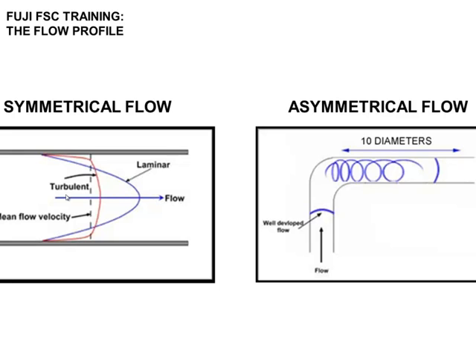The symmetrical flow profile is basically when you draw a center line down this, the top half of flow equals the bottom half of flow. And this situation will occur if I have an elbow, 10 pipe diameters, put my sensor here, another 5 pipe diameters and an elbow here, at flow rates of around 10 feet per second. Higher flow rates, more straight run of pipe.